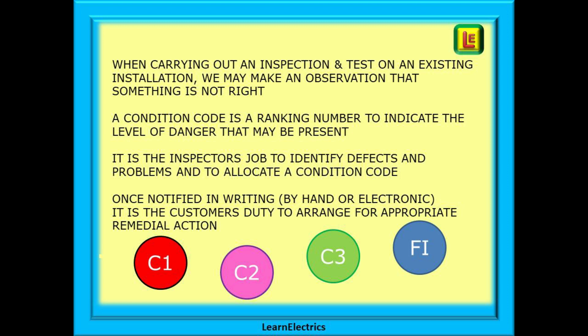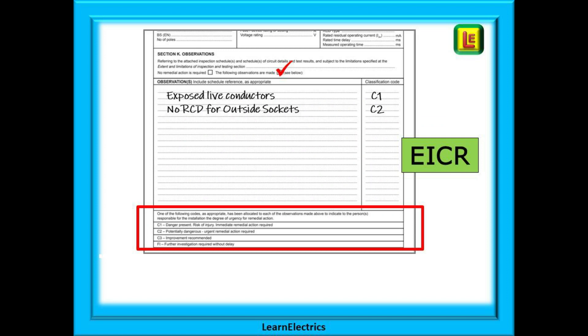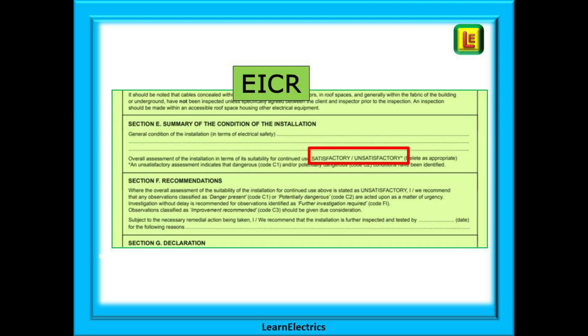Once notified of the observations in writing, either by hand or electronic, it is the customer's duty to arrange for appropriate remedial action. On the EICR reporting sheet you will record any observations and allocate to them a code number that indicates in your opinion the level of danger of electric shock or risk of fire. You will then make a recommendation: is the installation in a satisfactory condition and deemed safe for continued use, or is the installation unsatisfactory because one or more safety issues have been observed?